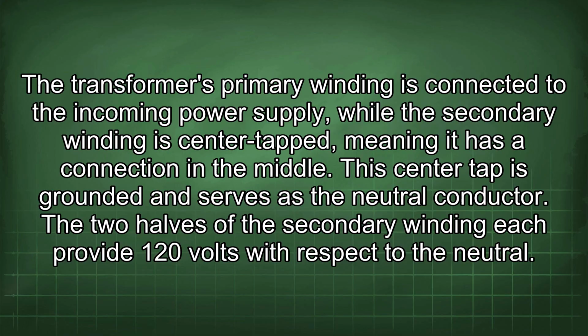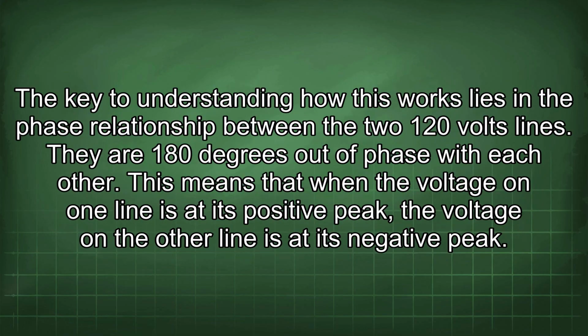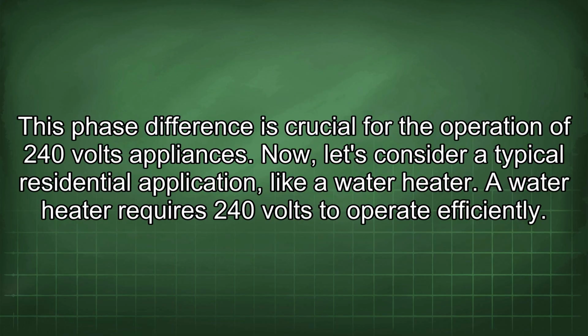This center tap is grounded and serves as the neutral conductor. The two halves of the secondary winding each provide 120 volts with respect to the neutral. The key to understanding how this works lies in the phase relationship between the two 120 volt lines. They are 180 degrees out of phase with each other. This means that when the voltage on one line is at its positive peak, the voltage on the other line is at its negative peak. This phase difference is crucial for the operation of 240 volt appliances.